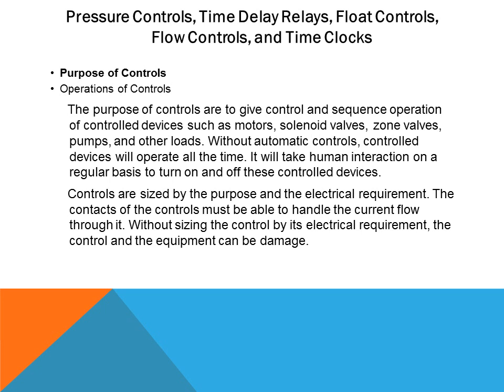The purpose of controls is to provide sequence of operation for controlled devices such as motors, solenoid valves, zone valves, pumps, and other loads. Without automatic controls, controlled devices would operate all the time, requiring constant human interaction. Controls are sized by their purpose and electrical requirements — the contacts must handle the current flow, and improper sizing can damage the control and the equipment.